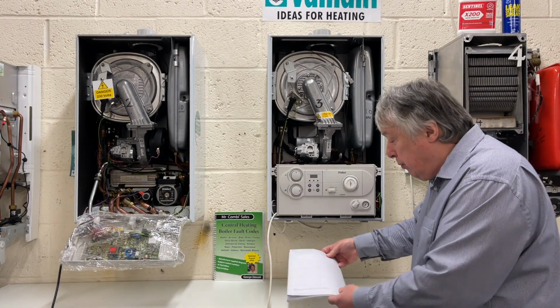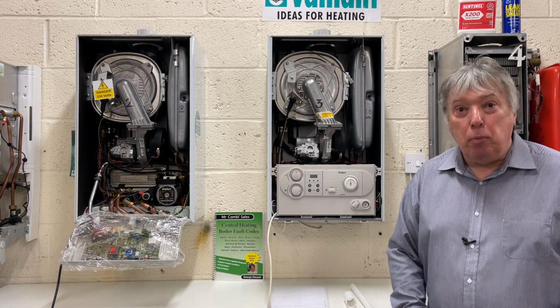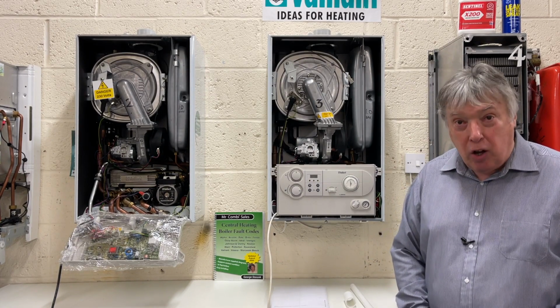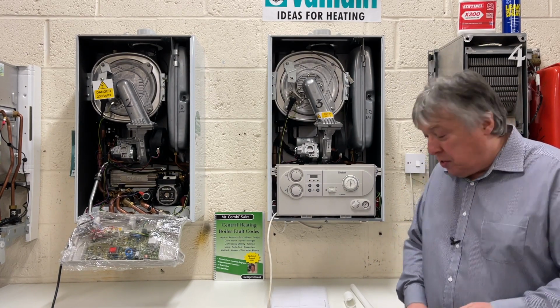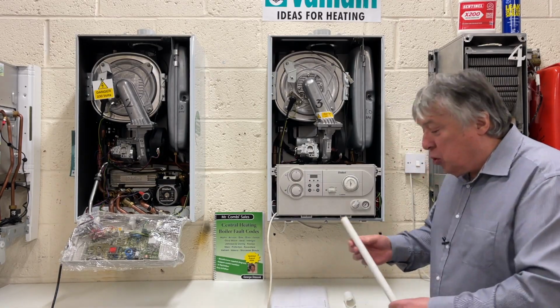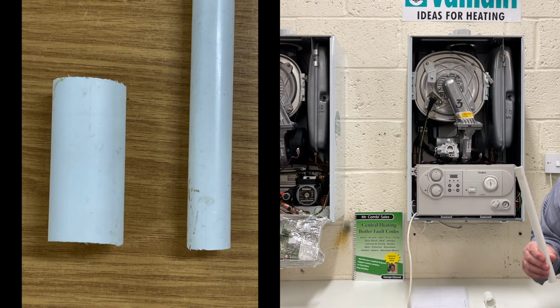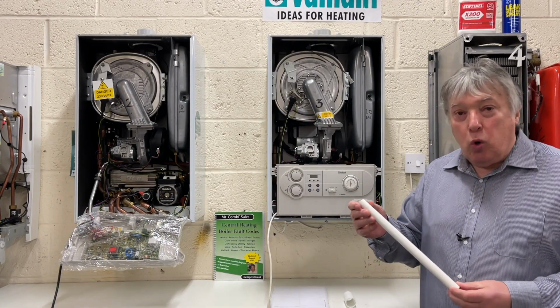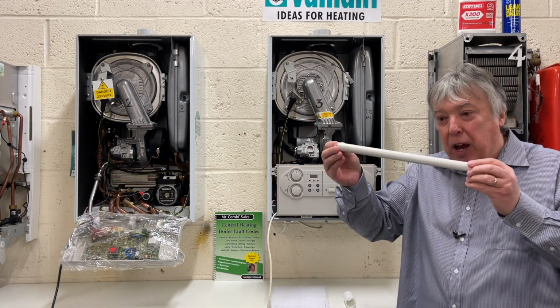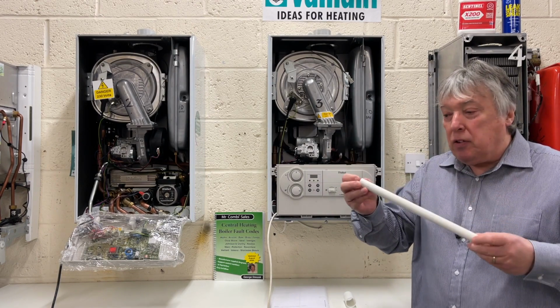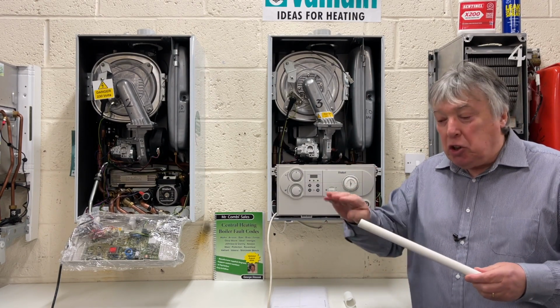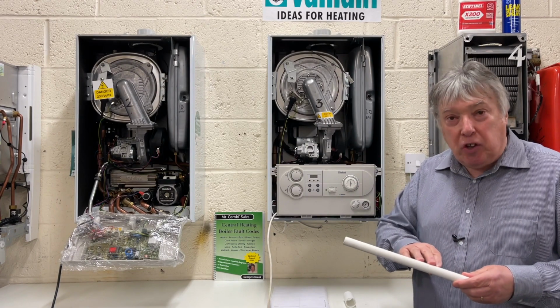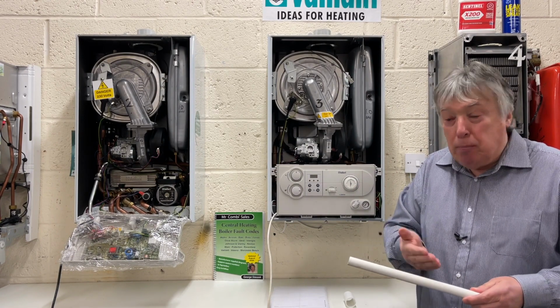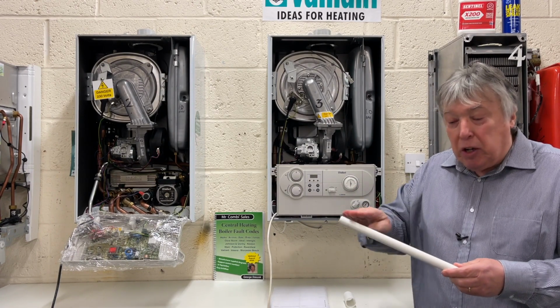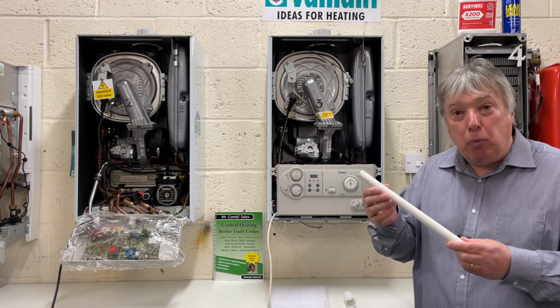But also, F28 could be a frozen condensate pipe outside. And this happened a few years ago when we used to install these overflow pipes through the wall and down to the drain. And some installers would have a very shallow drop, and some boilers, they just trickle down, and if it's frosty, which is going to be December to March basically, it will gradually build up that layer and this pipe would freeze.